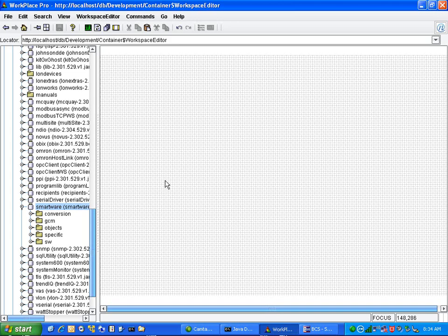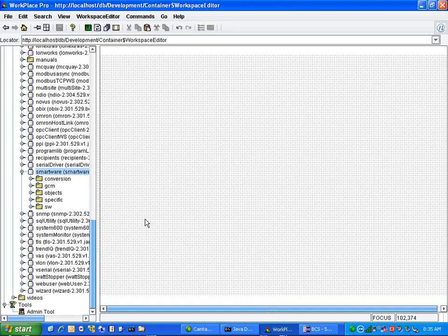There's a couple that I commonly use in the BACnet world these days. What I like about them is you can use other objects to get around it, but the conversion objects are nice and small, and they're easy, and they make your programming look a little neater and nicer to the eye, as opposed to using a big fat math object just to convert a float status into a float priority.